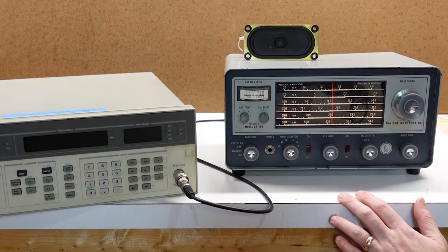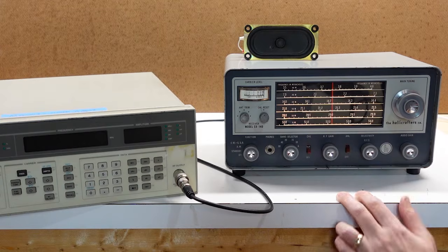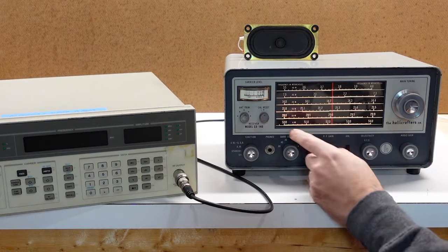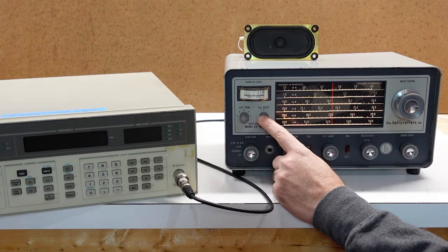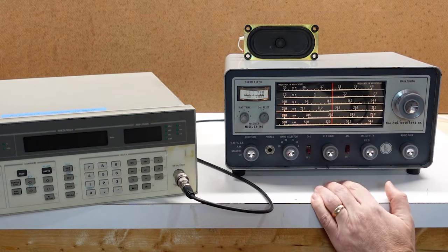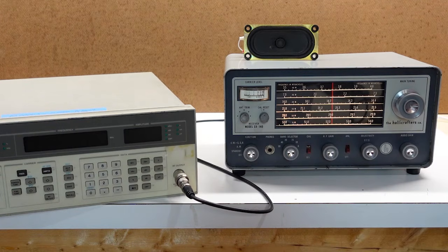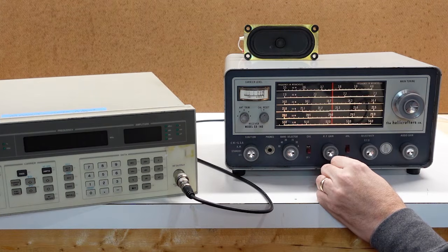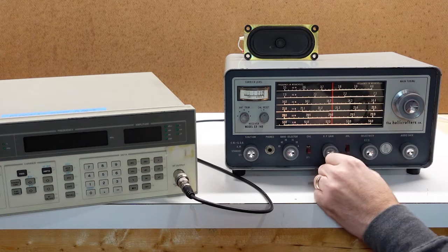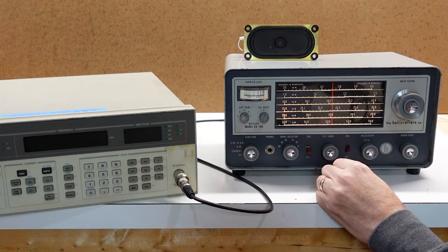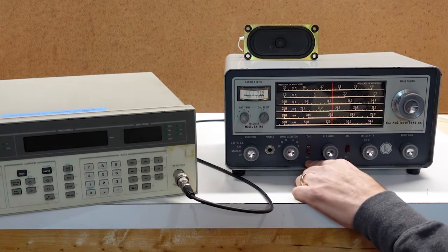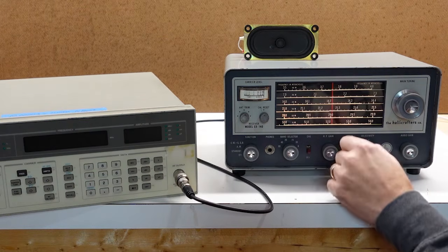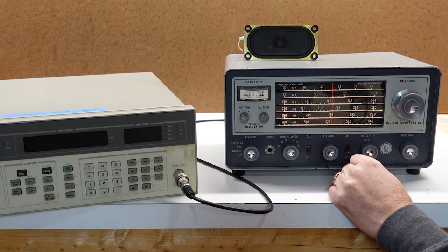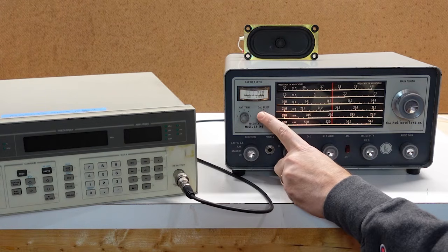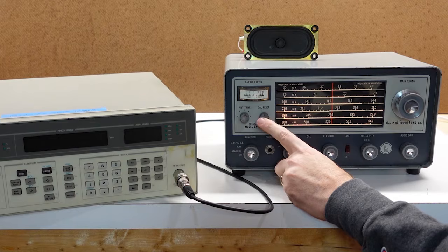So per the manual, I'm going to do the procedure for setting the calibration of the dial pointer, and that's this control right here for cal reset. But as I said, it's incredibly touchy, so I don't know how practical this would be in trying to use it in operating conditions where you're trying to bounce it back and forth between bands. But nevertheless, the way it works is you flip the switch here from off to cal, and that engages the calibration oscillator circuit. But then it's this dance between an incredibly touchy cal reset control.